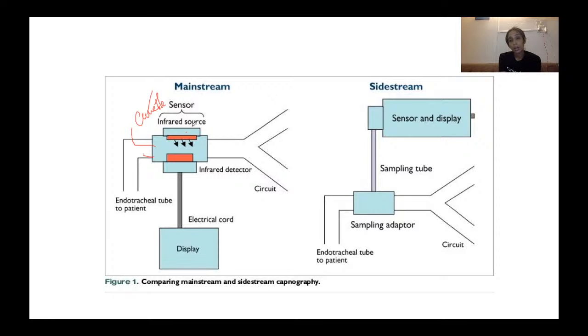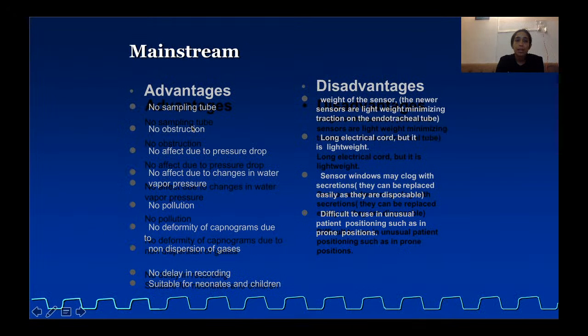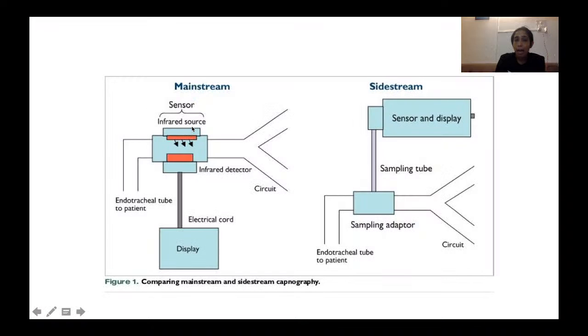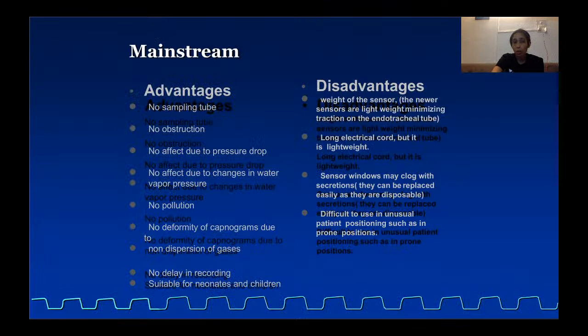There is no lag time because it is located in line with the gases that are going to the ventilator. Basically no disconnections can occur because there is no sample tube, so there are no complications associated with the sample tube, like obstruction and pressure drops, then changes due to water vapor, because nothing is clogging it. Of course sometimes, like I said, the sensor can get clogged with water vapor.